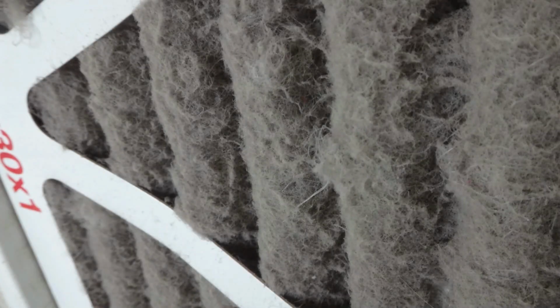Now if you have a temperature difference that exceeds that 22 degrees, it usually indicates that the airflow across the evaporator coil may be too slow. This can be for multiple reasons. This could be you have an issue with the blower itself, it could be a dirty evaporator coil, it could be a very dirty filter, but something is slowing down the airflow when it should be running at full capacity, and these excess numbers are cluing you in that there's an issue that needs to be looked at. Now sometimes it can also be a system that's simply overcharged. There's just too much refrigerant in it.